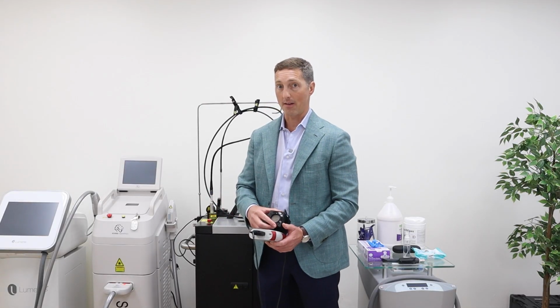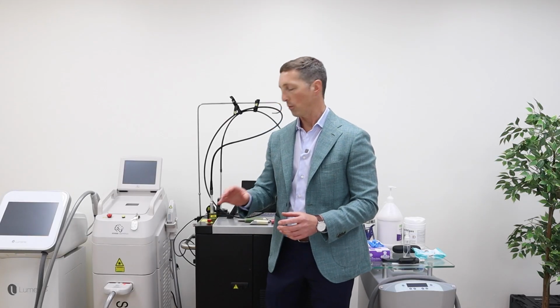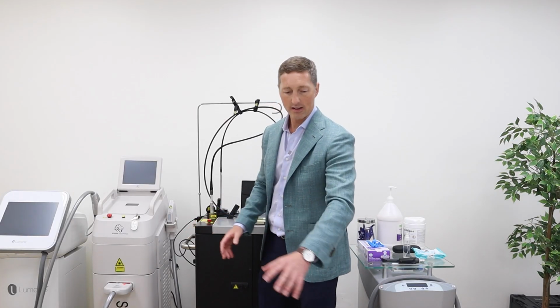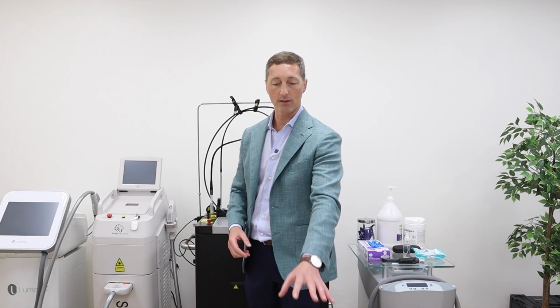Imagine for a second that it's not. And we've seen this because we've done a lot of training over the last 12, 14 years at clinics where they have multiple locations within the same city, certainly 4 or 5 laser systems with the same practice. And what ends up happening is that one system gets serviced by a technician and this is performed and the verification is correct, but the next system gets performed, or the next system when going into service many months later is perhaps serviced from a different technician or a different external power meter. And as a consequence, one system might be right on and the other system might be up or down as much as 20%, which is incidentally what the FDA actually allows. A little bit scary because that's a huge degree of difference, right?